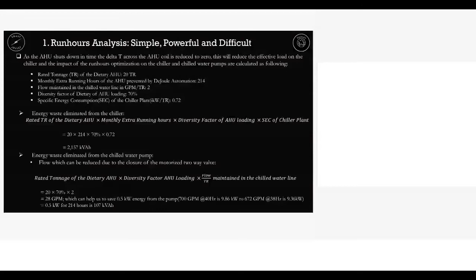So as an aftermath of all these activities, this is the energy we save. From the chiller we save some energy, from the pump we save some energy, from the AHU we save some energy. This is the impact of a simple running hours analysis on a small AHU, a 20 TR. 1 TR is 400 CFM, that is a thumb rule. So a 20 TR air handling unit of 8000 CFM capacity with a 5.5 kilowatt blower motor sitting within. This is the saving we are able to capture from a single motor in a centralized air conditioning plant, which also fetches savings from the chiller and pump.